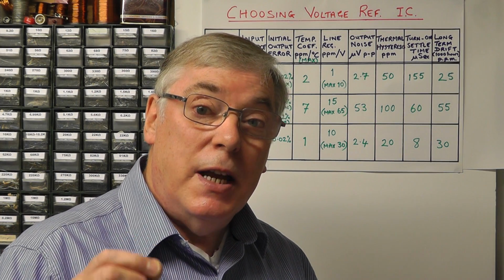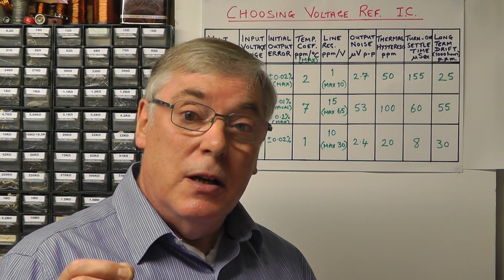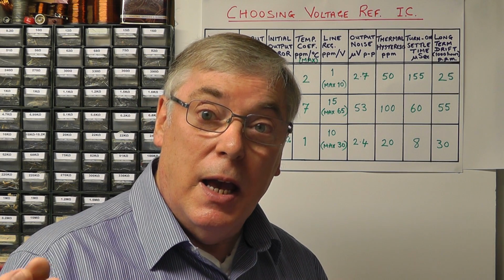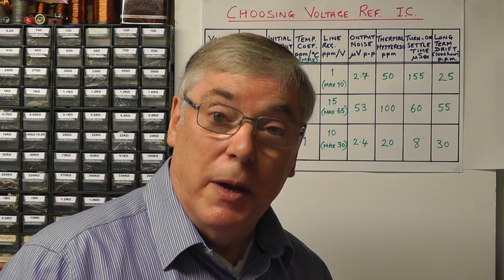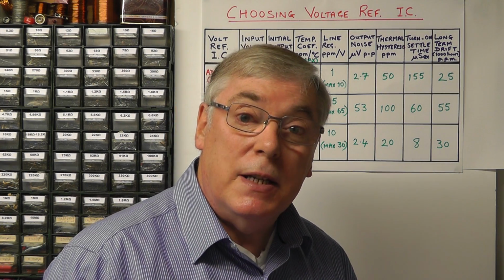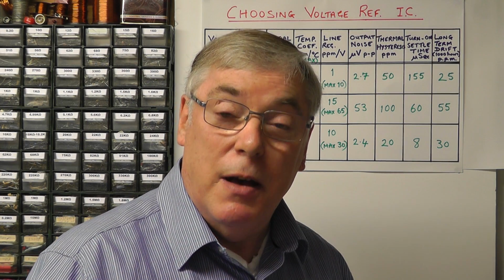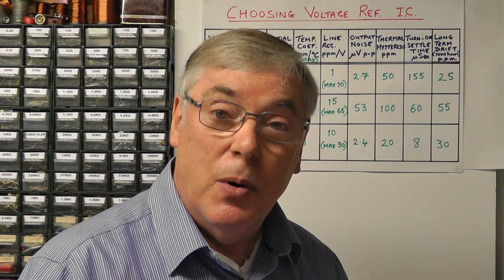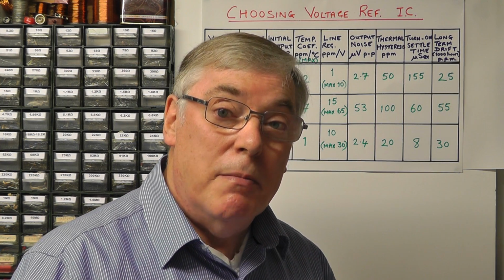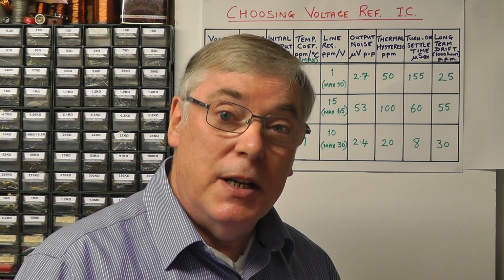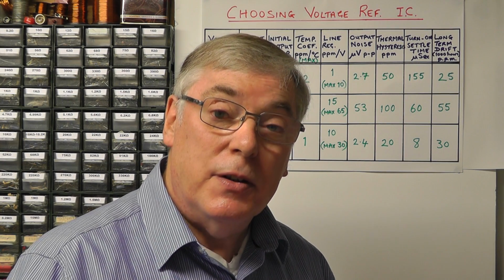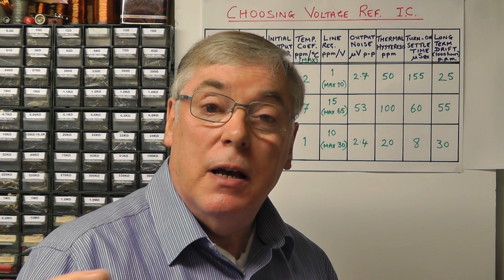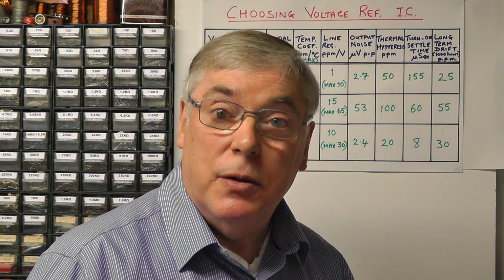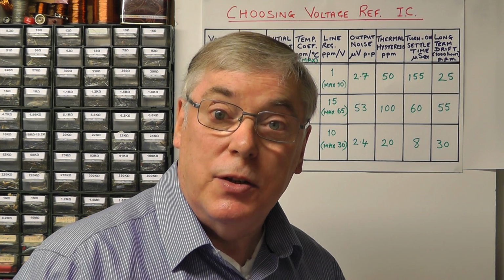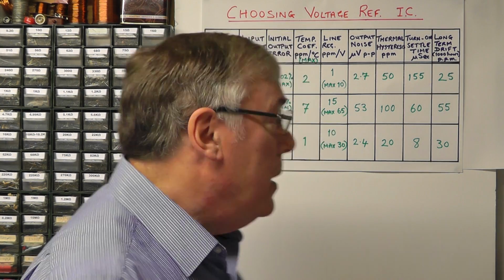But accuracy is not always the important factor when looking at things like a digital voltmeter. The reason is it's the long-term stability of that meter over time that's important. Also, any inaccuracies in the initial voltage reference can actually be cancelled out by calibration, by adding some offset voltage.